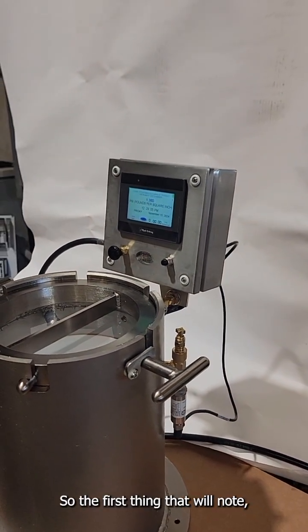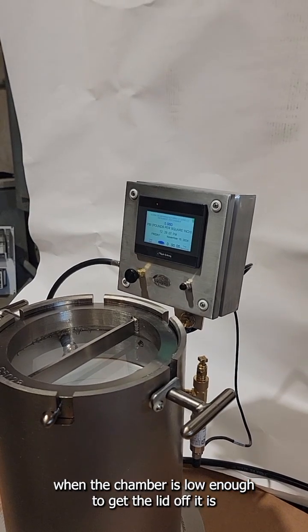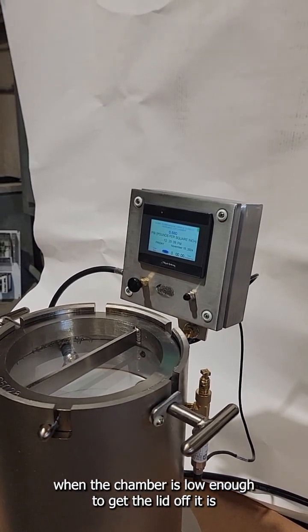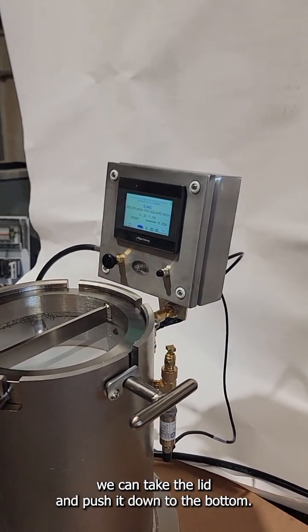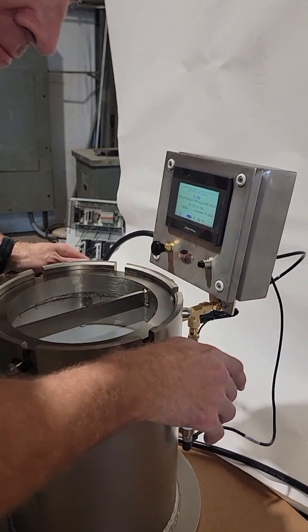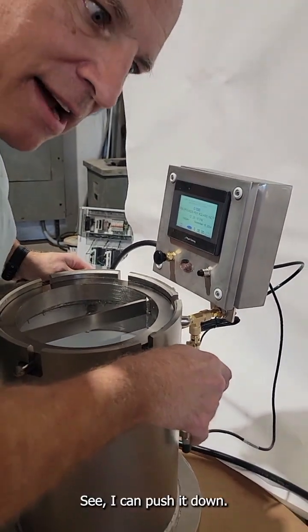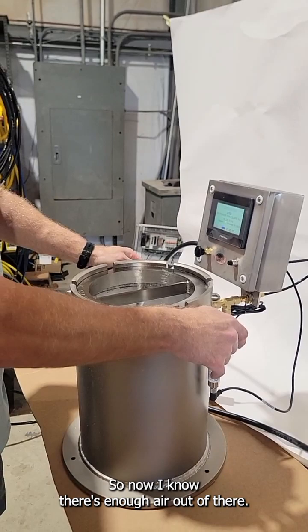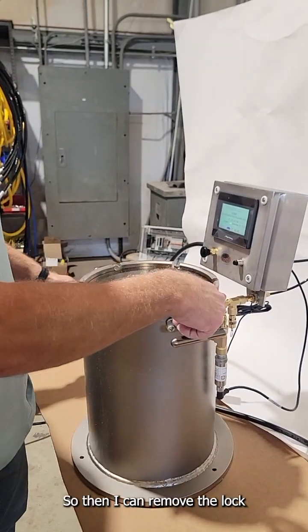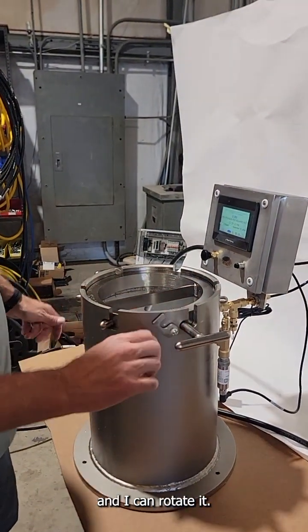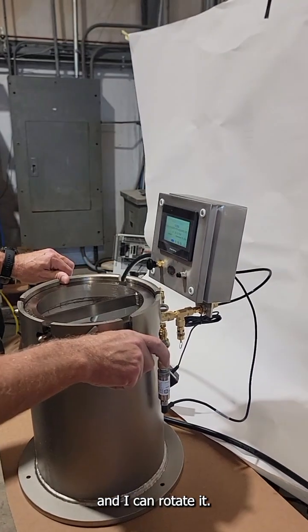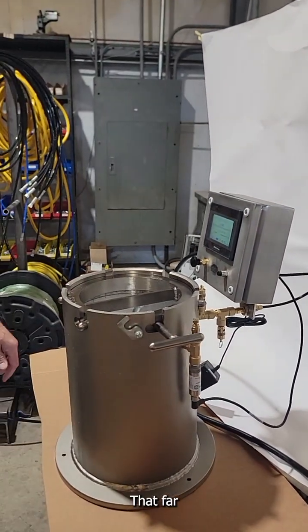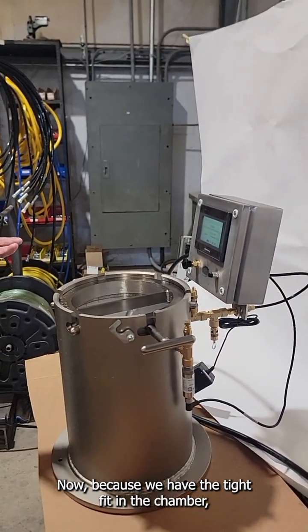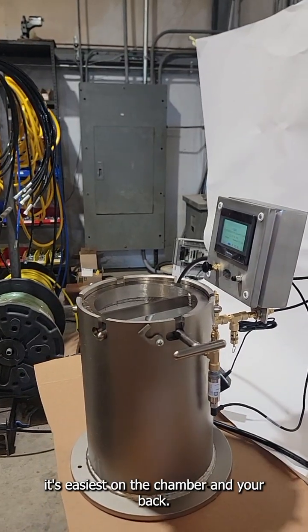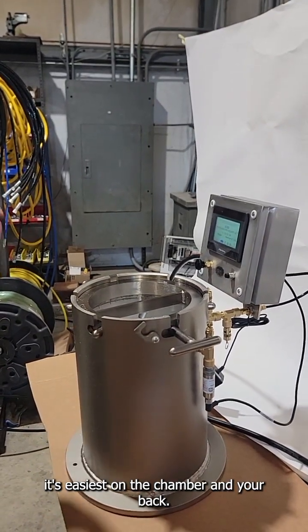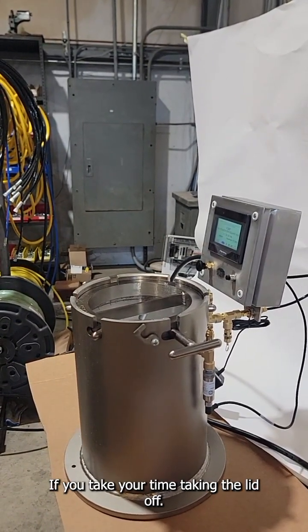So the first thing that we'll note when the chamber is low enough to get the lid off is we can take the lid and push it down to the bottom. See, I can push it down. So now I know there's enough air out of there. Then I can remove the lock and rotate it that far. Now, because we have the tight fit in the chamber, it's easiest on the chamber and your back if you take your time taking the lid off.